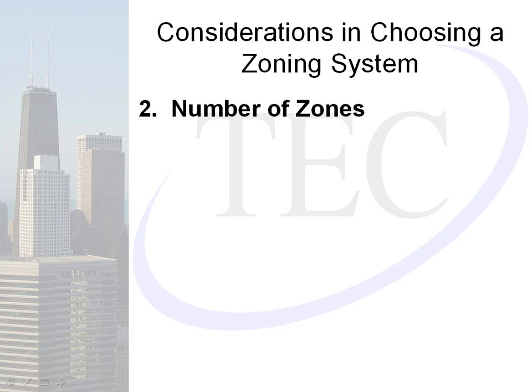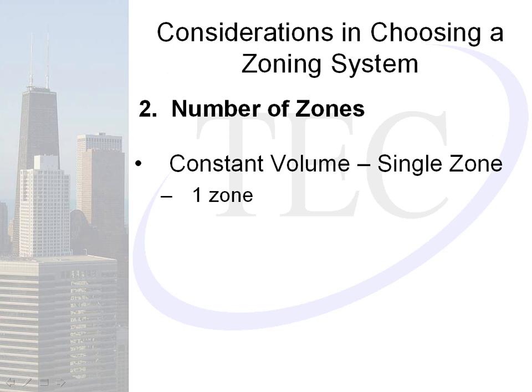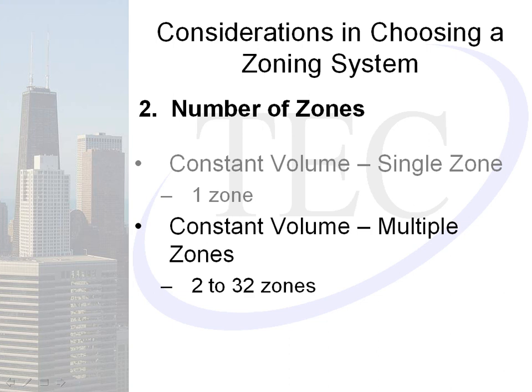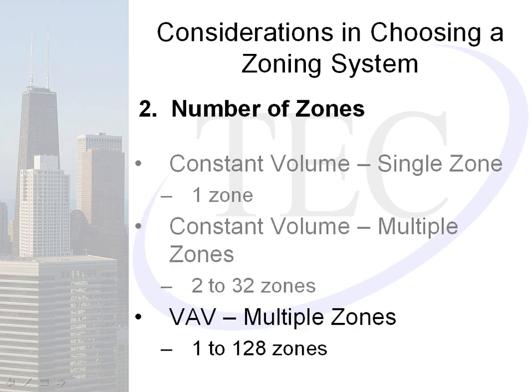The second consideration is the number of zones. Constant volume single zone is only one zone — one thermostat, one source of control. Constant volume multiple zones can be anywhere from two zones up to thirty-two zones, though typically twelve zones or under. VAV multiple zone would be anywhere from two to one hundred twenty-eight zones. There is a new rooftop unit — the new PD — that provides single zone VAV as well.